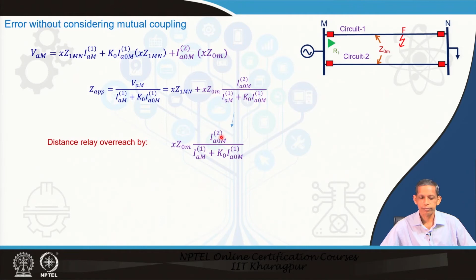Now, let us go to an example. So, we have a double circuit line as shown, a radial system, and we have Z 0 m f. The Z 0 m f corresponds to the zero sequence mutual impedance up to the fault point for this circuit with circuit 2. This is a 230 kV system, 150 kilometer, and we have line parameters Z 1, Z 0 and Z 0 m, the mutual zero sequence impedance, and the fault is being created at 100 kilometer. Therefore, the corresponding Z 1 positive sequence impedance up to the fault point, which the relay is expected to obtain as Z apparent, becomes 100 into this per kilometer impedance. So, that gives us 3.6 j 51.27 ohm.